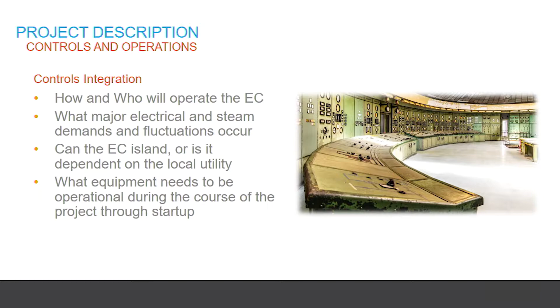Another key component to this upgrade was the controls integration. This facility that Eastern Michigan has is a building with boilers in it and this aged Solar Taurus 60 and HRSG. Over the course of design, construction, and ultimately commissioning and startup, the boilers had to stay operating, providing steam to the campus, and they had to purchase electricity from DTE. So it was important to understand where we could take outages, when those outages had to occur, and also keep everything online so they could continue to provide steam and electricity to the campus.